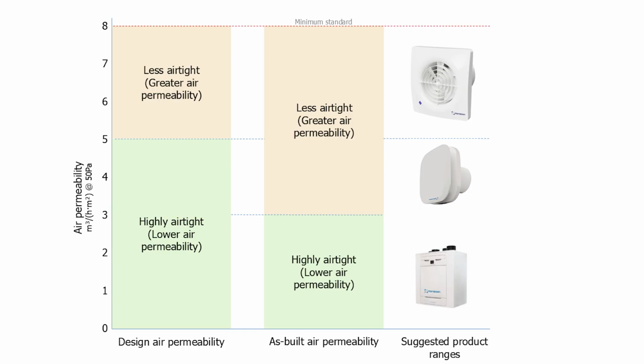Or a continuous mechanical extract ventilation system should be installed. Continuous mechanical extract ventilation is for between 5 and 3, CMEV centralised and DMEV decentralised. And anything below 3 should be MVHR. The graphic here shows the value at which the building changes from less to highly airtight, which varies depending on whether it's an as-built or design air permeability.